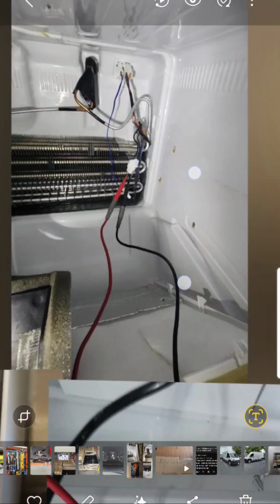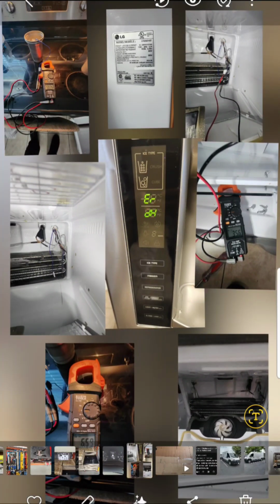And by the way, the thing with this unit was that it was still freezing well in the freezer and the refrigerator, so I didn't have like a legitimate refrigeration issue to cause, or an issue with the defrost heater. It was more so that probe was not in place. It wasn't in its proper place, so it wasn't detecting the transfer of the heat from the heater coil when it was in defrost mode, and the computer wasn't able to calculate that it had defrost in its allotted time. So that brought up the error.